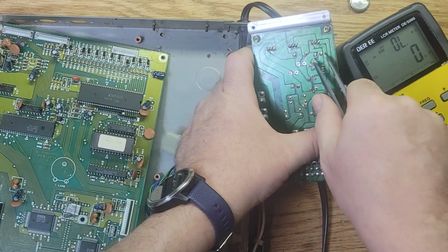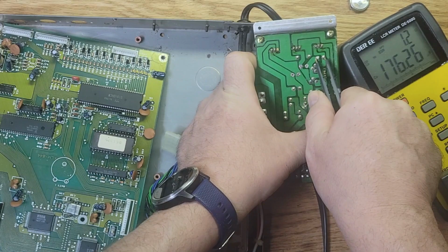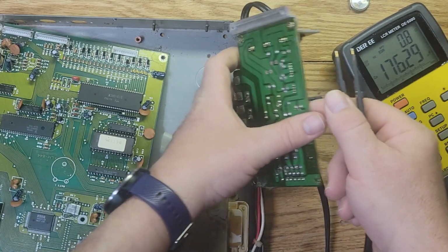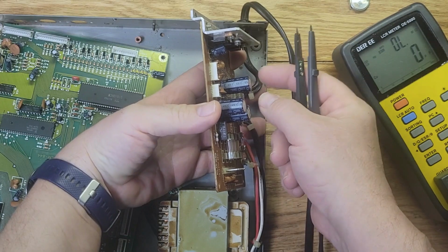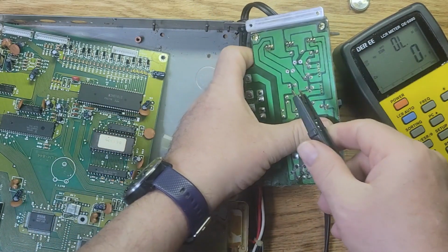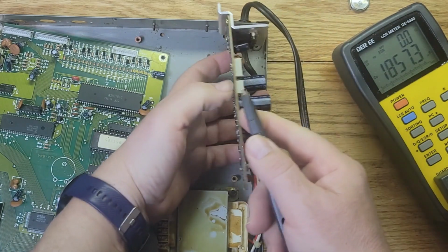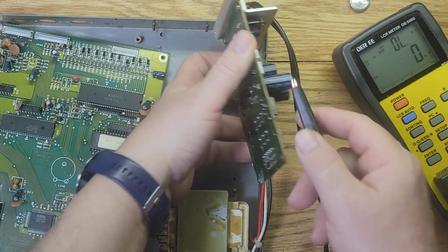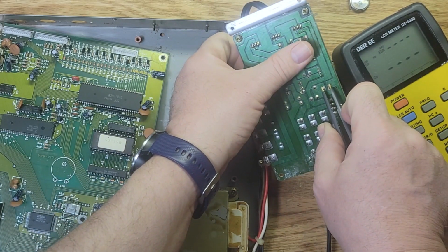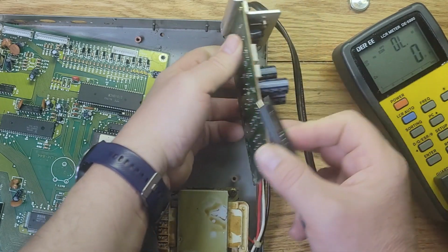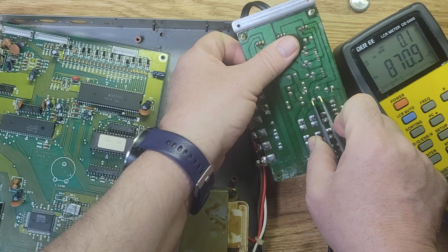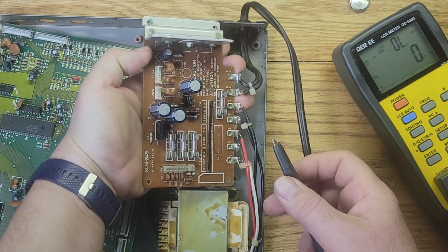So let's check the rest of them. 176 microfarad, and that's the other 220 microfarad. Let's check this one right here. Okay, that should have been a 2000 microfarad, so that was close. And this should be a 1000, and it's 860, so that's within 20%. This one is 869. So the capacitors are all within their tolerance, so I don't think that's what caused this to fail.